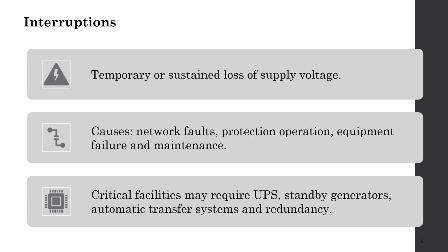Then we talk about interruption, a temporary or sustained loss of supply voltage. This is caused by network fault, protection operation, equipment failure, and maintenance. For this scenario, we can use mitigation plans: critical facilities may require UPS and standby generators, automatic transfer system, and redundancy. Redundancy means each backup unit should have duty and standby supply.